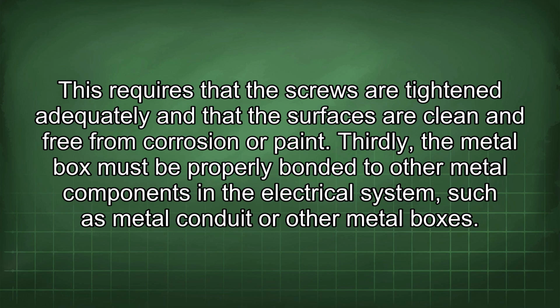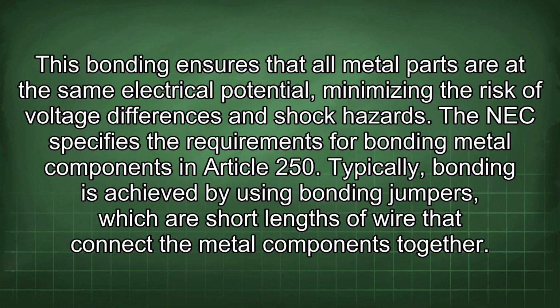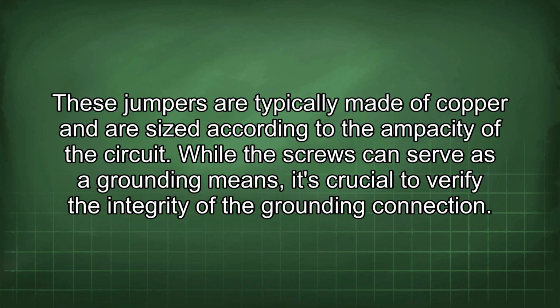This bonding ensures that all metal parts are at the same electrical potential, minimizing the risk of voltage differences and shock hazards. The NEC specifies the requirements for bonding metal components in Article 250. Typically, bonding is achieved by using bonding jumpers, which are short lengths of wire that connect the metal components together. These jumpers are typically made of copper and are sized according to the ampacity of the circuit.